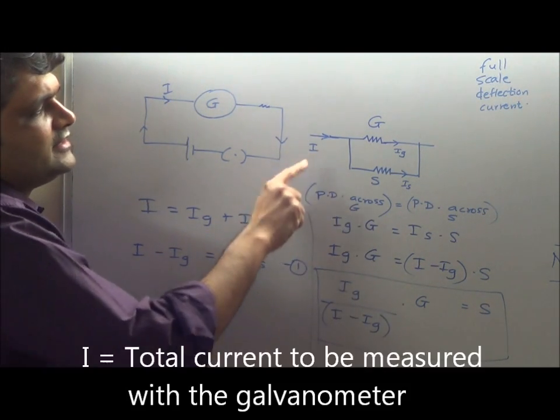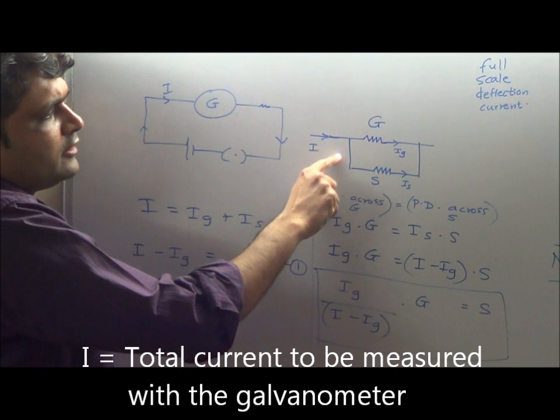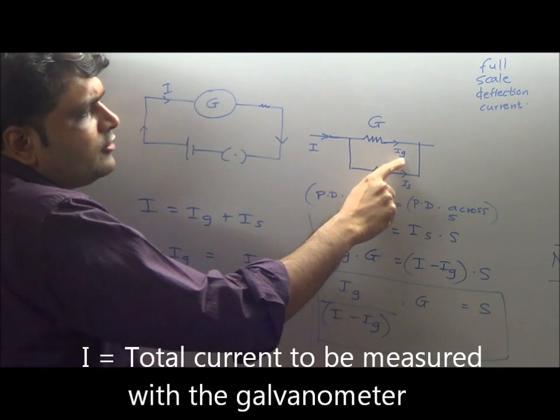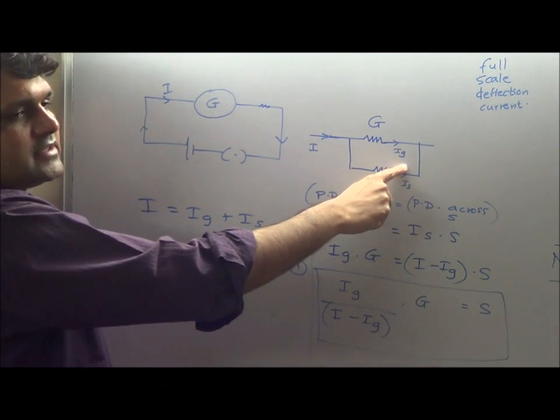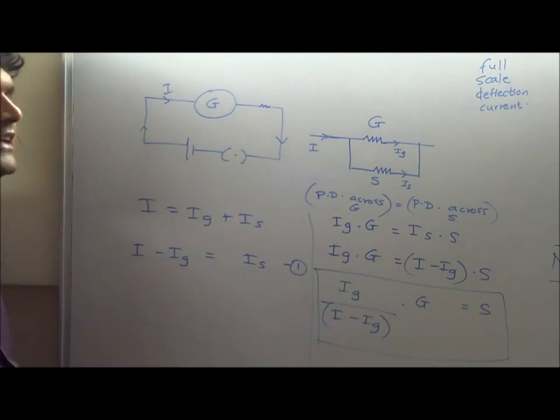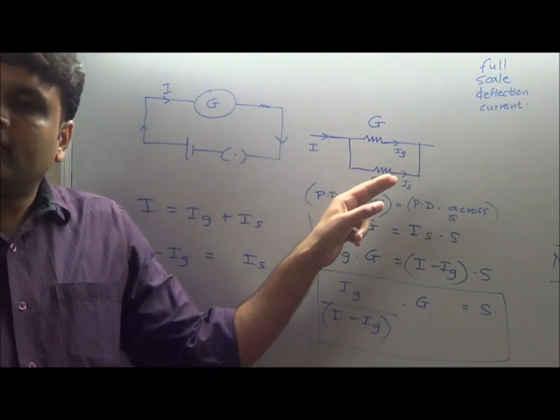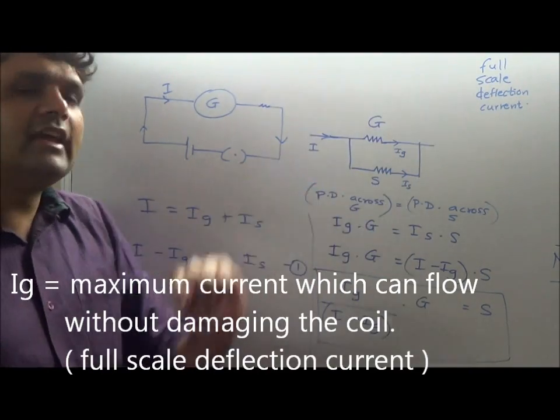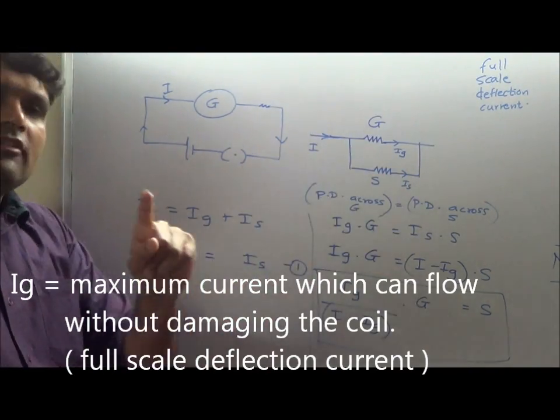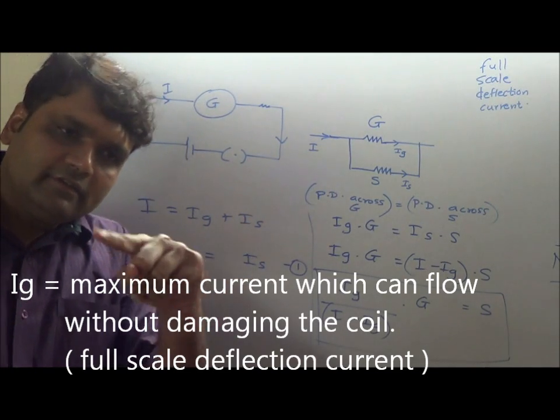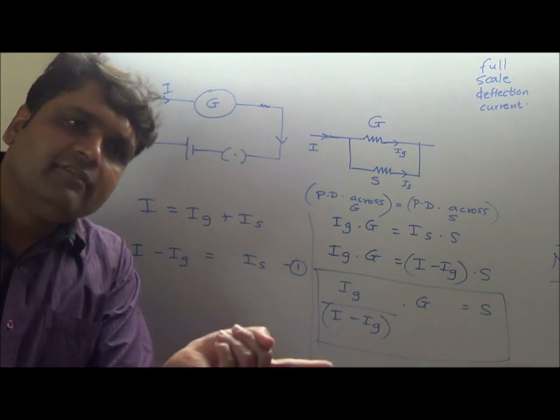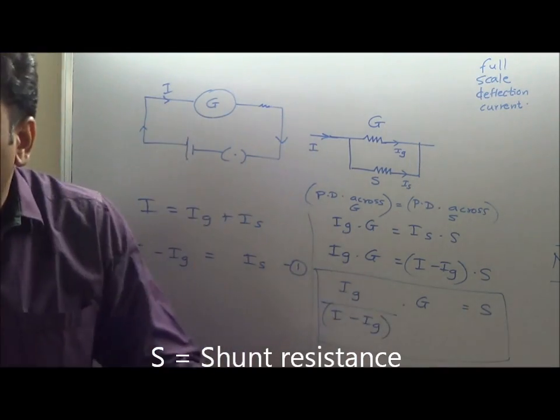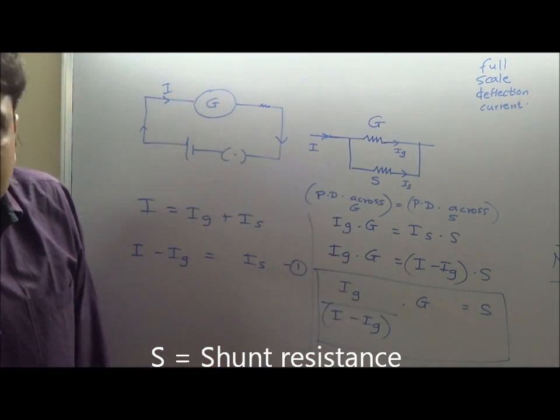Let's say the total current to be measured is I. Part of the current flows through the shunt — let's call it I_S — and part flows through the galvanometer coil — let's call it I_G. I_G is the maximum current which can pass through the galvanometer without damaging the coil; it is also called the full-scale deflection current, meaning the needle deflects across the entire scale. But I may want to measure currents larger than I_G, so I will be a value probably larger than that.